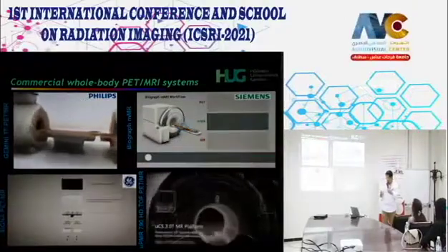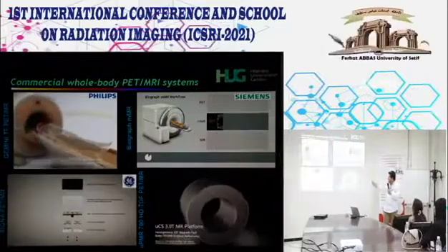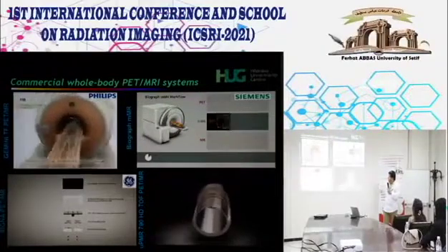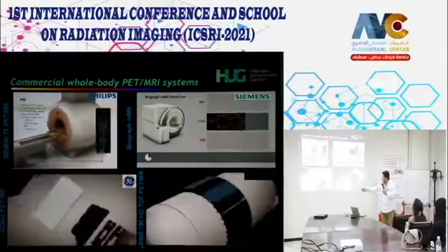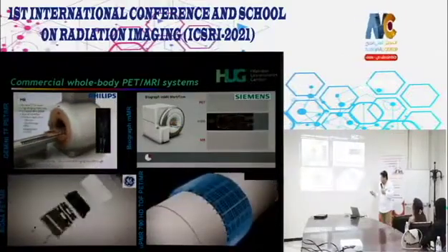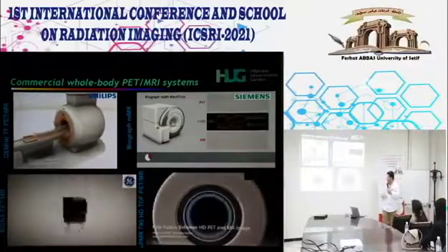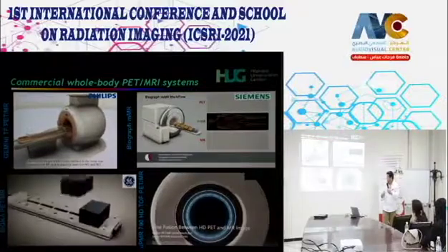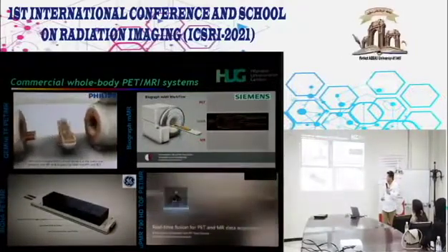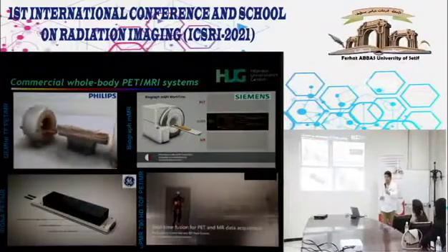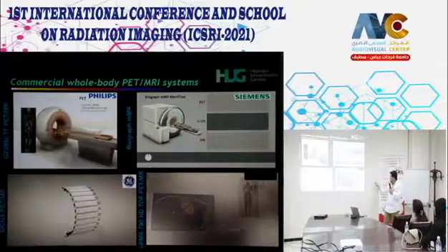And for those who attended the conference yesterday, I think I showed these different design concepts from sequential acquisition to simultaneous acquisition from Siemens, General Electric, who have a very interesting design concept. They use silicon PMs to enable the implementation of time-of-flight technology, contrary to the avalanche photodiodes, which have very low coincidence time resolution. So there is no way to get time-of-flight implemented on this type of technology.